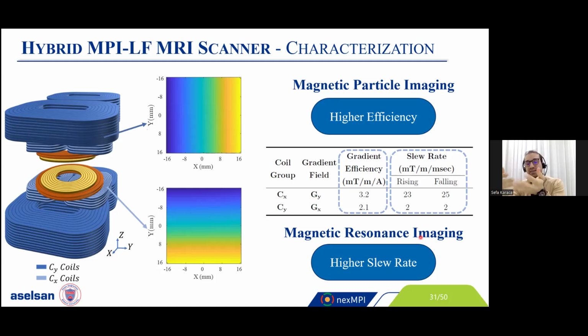As I said, slew rate is a measure of how fast you can switch your gradient fields on and off. For MRI, we require a higher slew rate, and if you have a lower slew rate, it restricts your pulse sequence capability. So you cannot apply different pulse sequences because of the lower slew rate, and this is the case for our system.